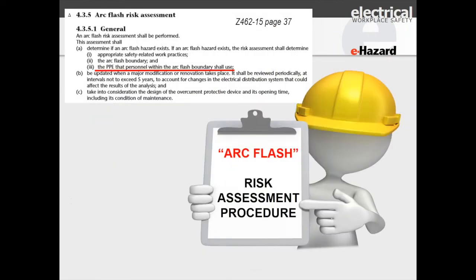And quickly, there's a little bit more too, but if you look at clause 4.3.5.1 on page 37 of CSA Z462, it says the arc flash risk assessment shall be performed. It'll determine if an arc flash hazard exists. It's either yes or no. If an arc flash hazard does exist, the risk assessment shall determine the appropriate safety-related work practices. Those work practices can and will and must be changed by the assessment of risk, depending on the condition of the equipment, the maintenance, and all those pieces we went through in the overview of step 2.